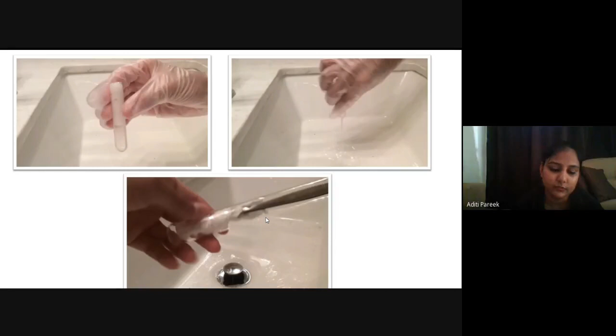For the pipettes, soak the pipettes in a cleaning solution overnight. Wash them in running tap water. Then we have to rinse them with distilled water. And the suction pump of the pipette should be cleaned thoroughly because this may be the most contaminated part of the pipette. For this, dry the suction pump using spirit or acetone, and we can also sterilize it if we need to. We can also sterilize the pipettes by plugging cotton wool in their mouth and wrapping them in paper and then sterilizing them in a hot air oven for 1 hour.